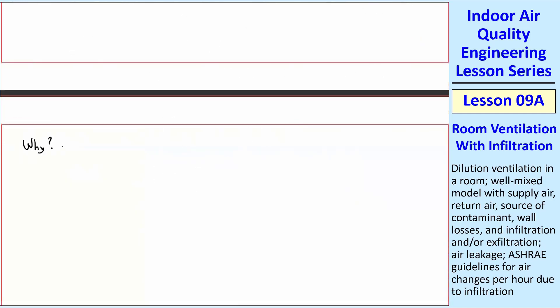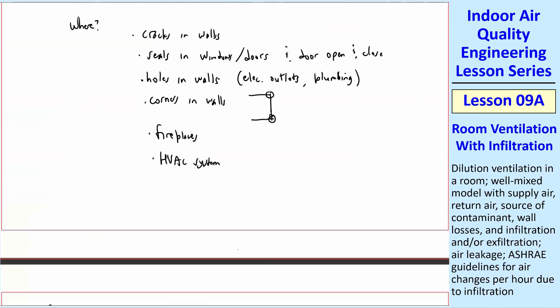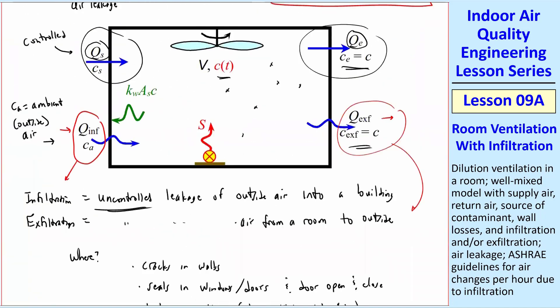Why is there infiltration and exfiltration? The simple answer is there's a pressure difference, delta P, between inside and outside. Delta P is P outside minus P inside. If delta P is positive, in other words, the outside is bigger than the inside, you're going to have infiltration. You have a high pressure outside and you have a low pressure inside. Air is going to seep through those cracks in the walls and come in.